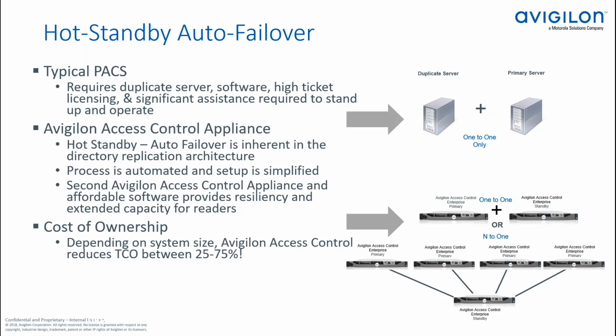Or you also could use this automatic takeover. The secondary server will monitor the primary server, pinging the primary server at certain intervals, which is configurable by the user. And if that communication is broken, so the primary server is down and the secondary server cannot reach the primary server in a certain amount of time, then the secondary server will automatically take over the system. So that's another method.